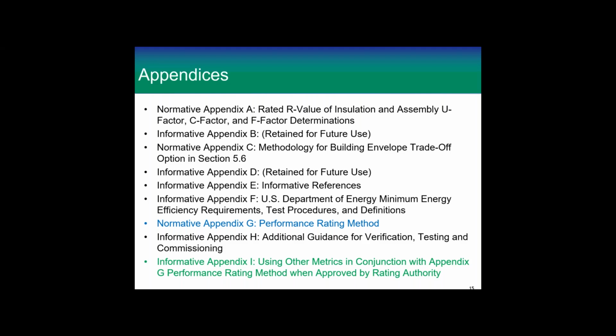Informative Appendix I is using other metrics in conjunction with Appendix G, the performance rating method, when approved by the rating authority. What that is: if you are a code official, and your jurisdiction wants to, instead of using cash money, which is what 90.1 uses, it's on dollar savings. If you would rather use carbon or some other metric than cash, the math that you would have to do is included in Appendix I. So it tells you how to convert to a different metric.